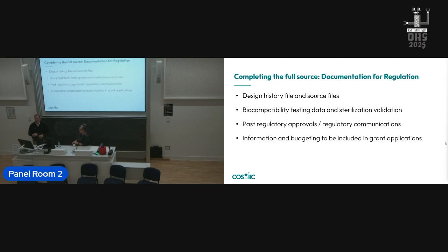There has to be a way to sterilize the device so that it can be clean and not cause infection in the participant. We've also found that providing documentation of our past regulatory approval from 2014, our IDE, others are able to work off of that to write their own application for an IDE. People in our research world also need the information to include in their grant applications so they can start working with our device.